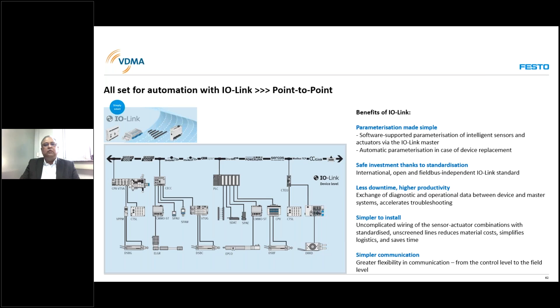Another big advantage of the IO link technology is that when a faulty device needs to be changed and replaced by a new one, the moment the new one is there, the PLC knows there is a new device, and it downloads all the parameters and data which were on the previous sensor, and the work is done. No need of reparameterization, no need of reteaching. That is the beauty of the IO link.